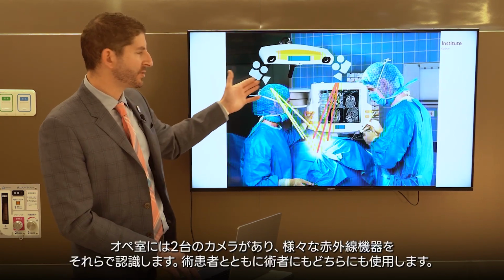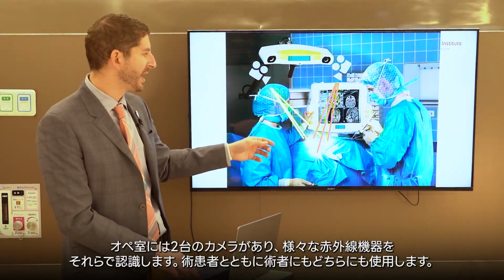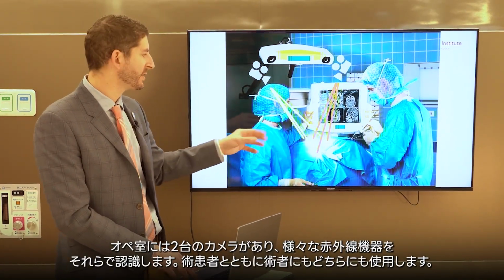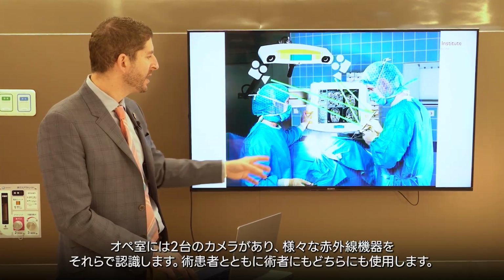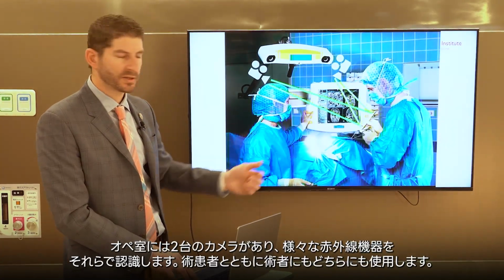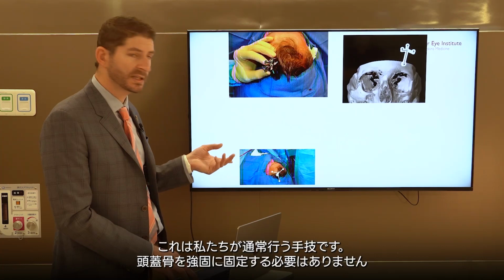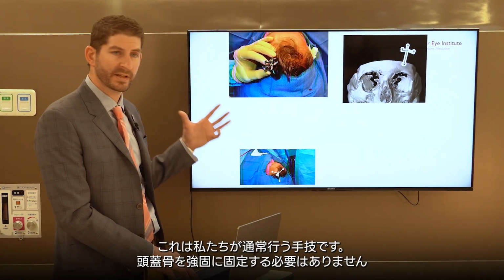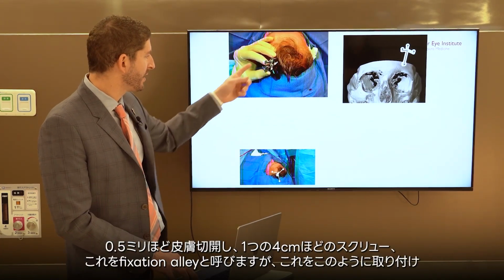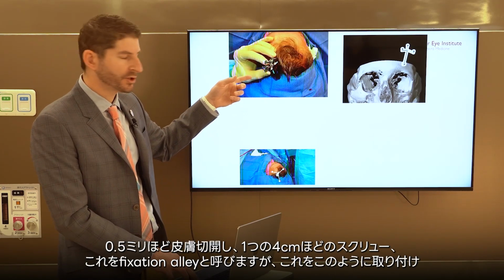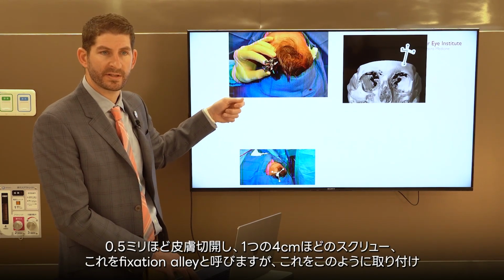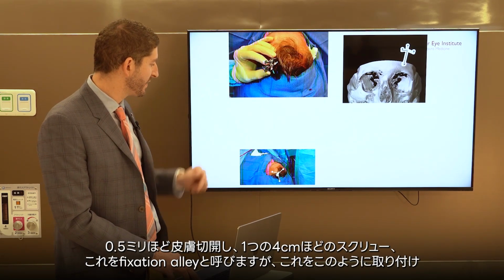In the operating room, they actually double it. You have 2 cameras, and then you have a variety of infrared bulbs that the cameras can see. Some are mounted to the patient, and some are mounted to the surgeon. This is the technique that I use. Rather than try to fixate the head, we use something that involves about a 0.5 centimeter incision and 1 single 4 millimeter long screw. This is called a fixation array.